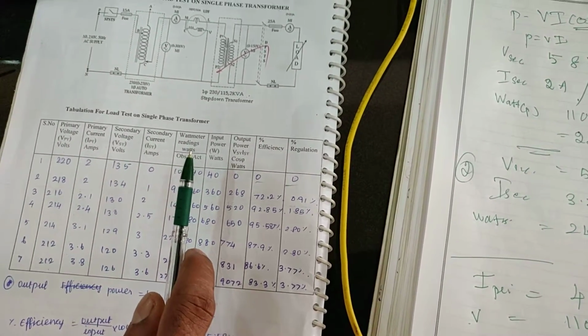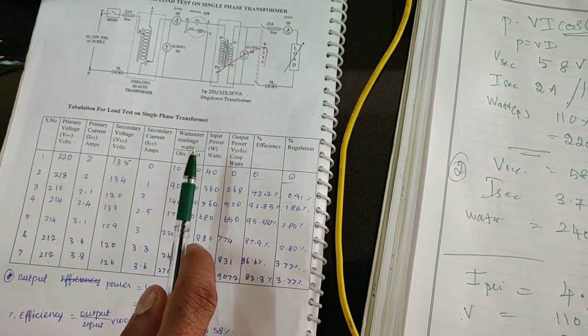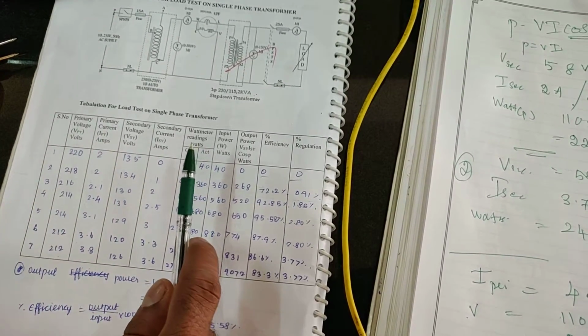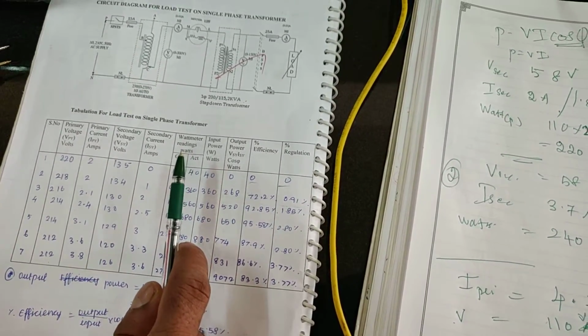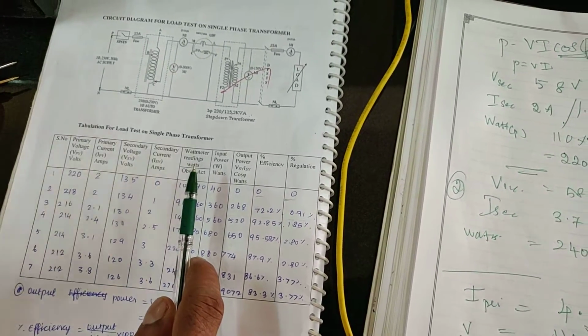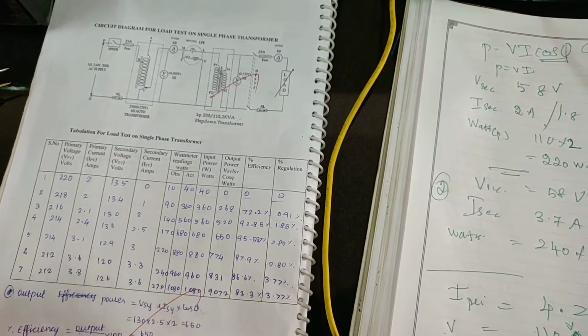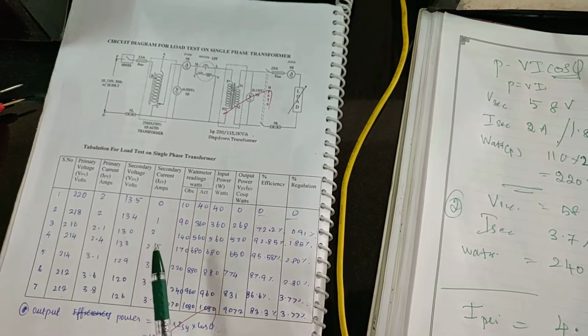Suppose you are going for an inductive or capacitive load, it is must and mandatory to connect the wattmeter on both sides, primary and secondary. In such a way, try to take 8 to 10 readings.